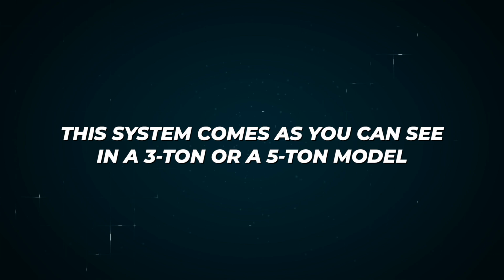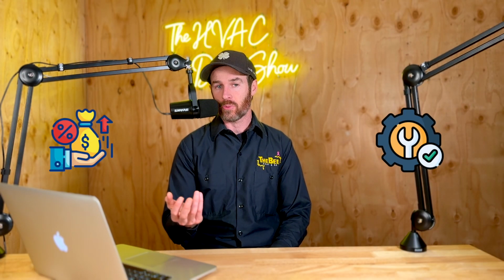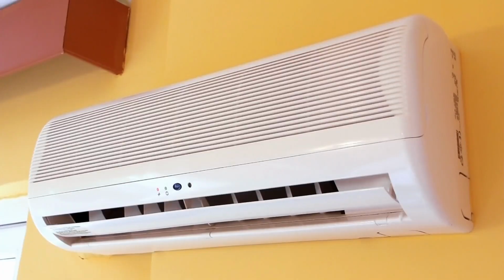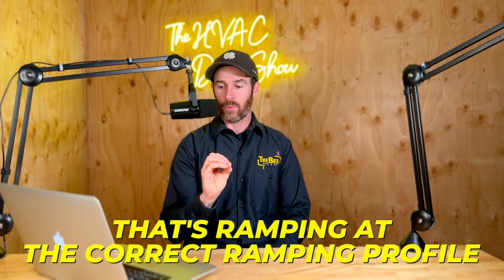This system comes in a 3-ton or a 5-ton model. There's something unique about this to consider: it doesn't mean if you need a 4-ton, you can't get this system. What's cool is you actually field set the tonnage during installation and commissioning. So if it's going into a smaller home where you only need a 2-ton system, you can buy the 3-ton unit, and the installer sets the tonnage in the field, so it's ramping at the correct profile when it's running.